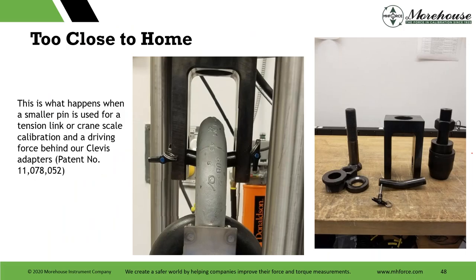Wrapping up: this is what happens when a smaller pin is used for tension link or crane scale calibration — the driving force behind our patent and kit. Our kit basically shows the pin size that should be used: small pin, large shackle — never a good idea with force measurements. Fortunately, no one died in that, and it's a few hundred dollars plus replacement cost.